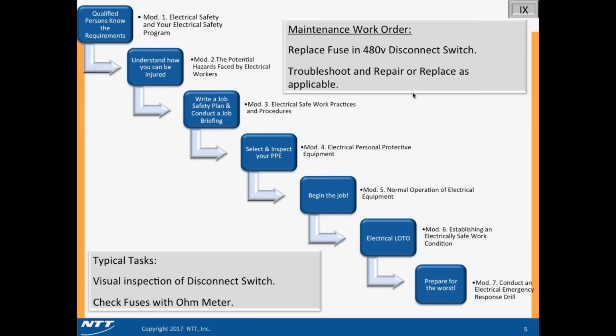If it's a disconnect, I know I'm going to have to get the door open to take a voltage reading, to take some amp readings, whatever I need to do, depending on what I'm trying to repair or troubleshoot. If it's a panel board, I know I've got to get the cover off, get the dead front off to be able to troubleshoot. Maybe I think I've got a bad breaker in this panel board.